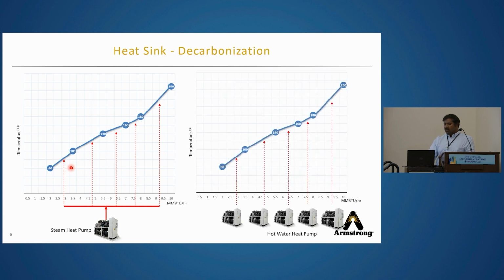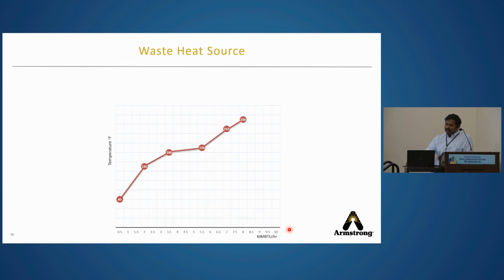So we can go for a mixture of a low temperature hot water heat pump to heat up a process to a lower temperature, a medium temperature heat pump for a medium temperature requirement, and a high temperature heat pump for a high temperature requirement. This set of heat pumps would be more efficient when compared to a steam heat pump. And these heat pumps can be installed locally, near the process. Even though capex would be a bit higher in this case, these heat pumps would still be much more efficient than a steam heat pump.